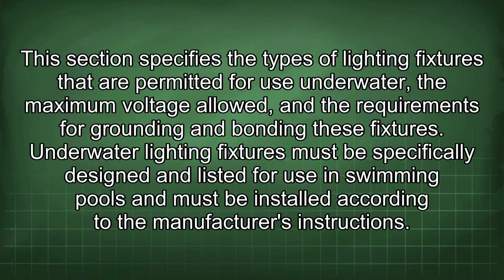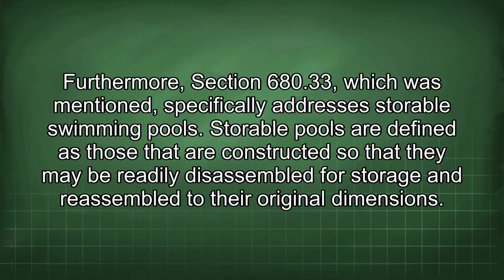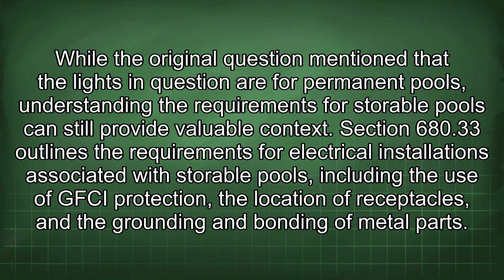Underwater lighting fixtures must be specifically designed and listed for use in swimming pools and must be installed according to the manufacturer's instructions. Furthermore, Section 680.33, which was mentioned, specifically addresses storable swimming pools. Storable pools are defined as those that are constructed so that they may be readily disassembled for storage and reassembled to their original dimensions. While the original question mentioned that the lights in question are for permanent pools, understanding the requirements for storable pools can still provide valuable context.